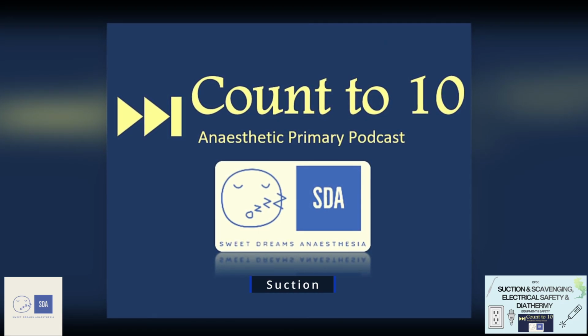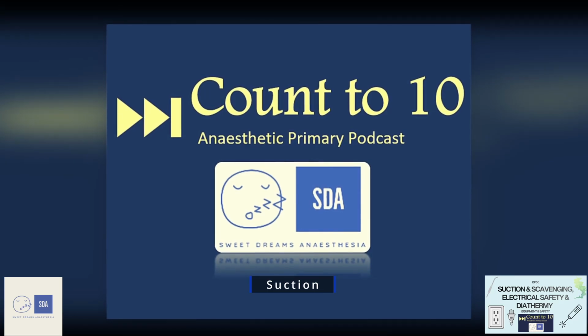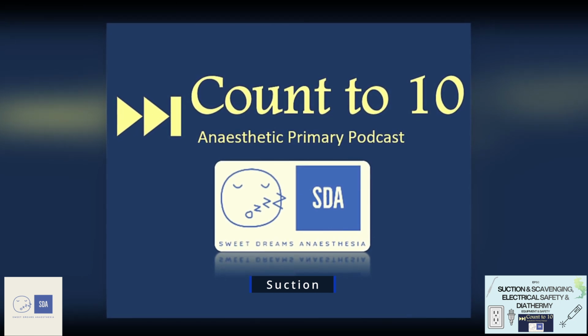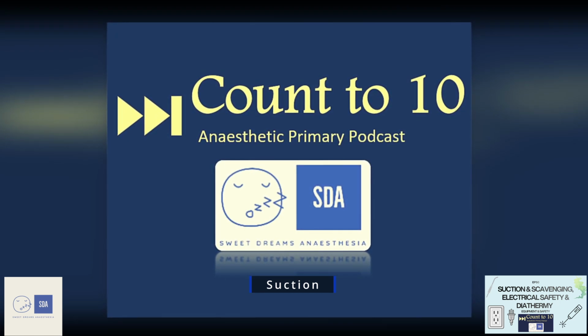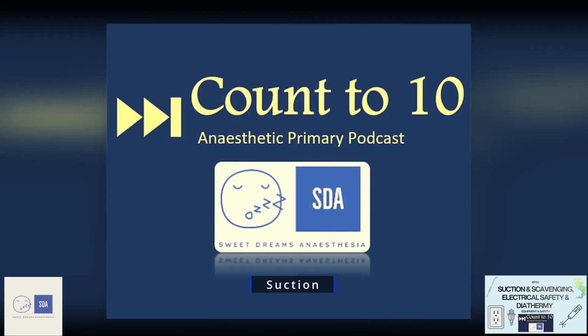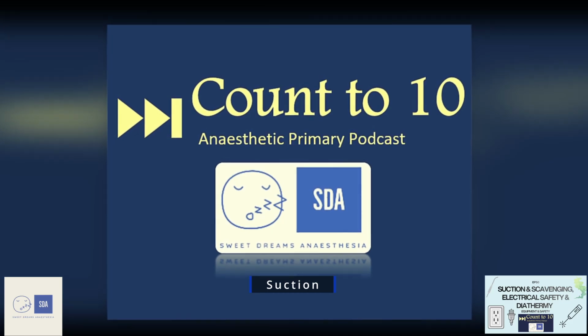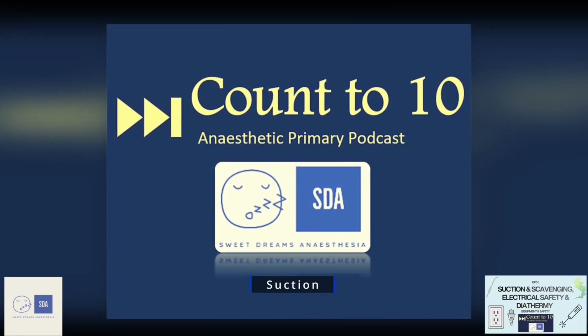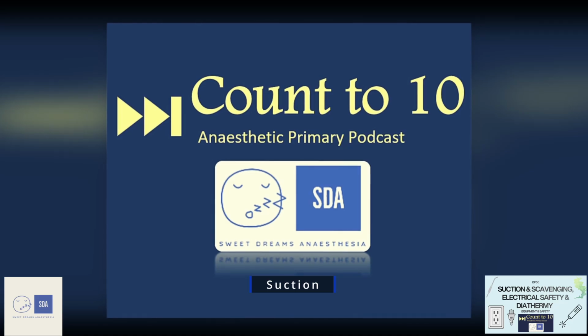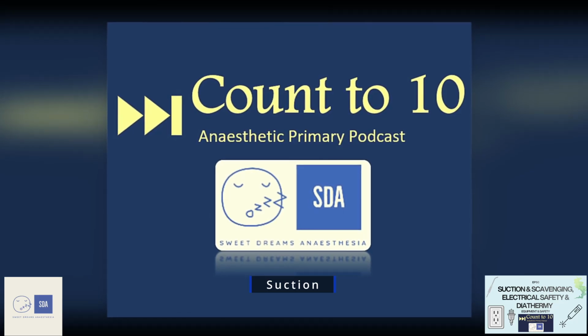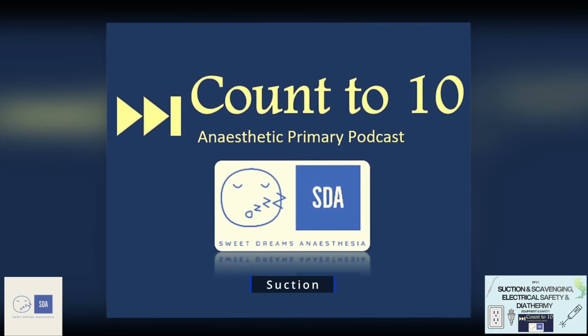Then your next essential component is your collecting vessel or your reservoir. This is what you see normally in a theatre setup. You have your collection canister next to your anaesthetic machine, or on the surgical side, they have the multiple collecting canisters. And again, the key thing here is recognizing how a suction device works, because if those things aren't tightly put on, then you're exposing it to air. And remember, you're trying to get rid of air within the vacuum. That's how the suction device works. That's why if things aren't tightly sealed, our suction doesn't work effectively.